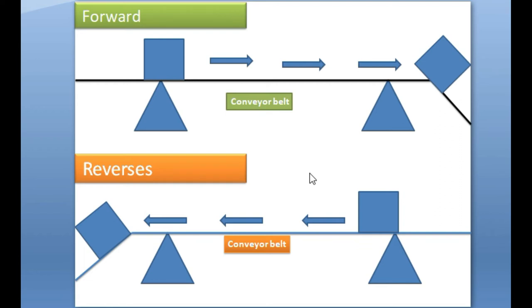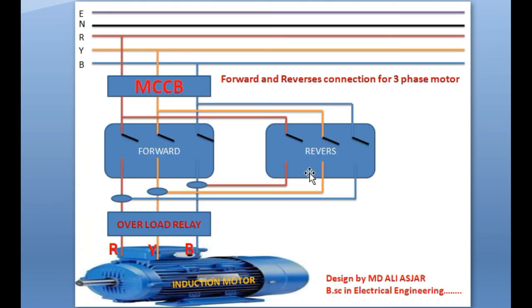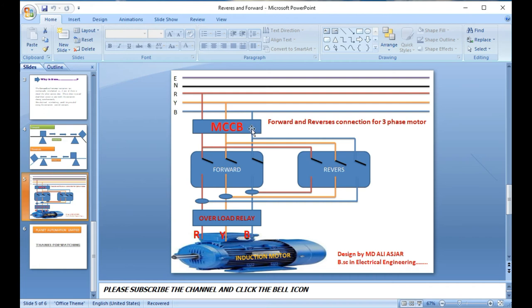This system is driven by a three-phase induction motor. Now let's go to the power block diagram of forward and reverse. We have the earth, neutral, and three-phase lines R, Y, B — red, yellow, blue. The MCCB (Molded Case Circuit Breaker) or MCB (Miniature Circuit Breaker) is connected directly to R, Y, B. For forward, the phases connect directly to the motor without any change. For reverse, any one phase is swapped, which causes the motor to run in the opposite direction.